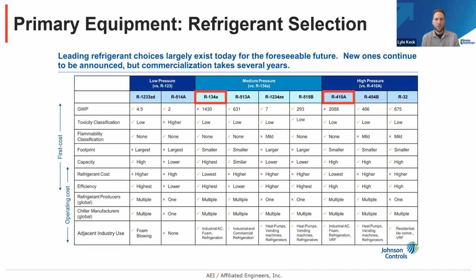You'll see here 134A and 410A, which are circled in red, are some of the more commonly used refrigerants with higher GWPs. Generally, we're targeting below sort of a 750 GWP or 600 GWP for a lot of the phase-downs and phase-outs. But what you'll see is that 513A or R-32 are just below that 750 threshold. These are kind of common drop-in refrigerants today, but it's not likely that we'll see those in 5 or 10 years as much, and we wouldn't really call them ultra-low GWP refrigerants.